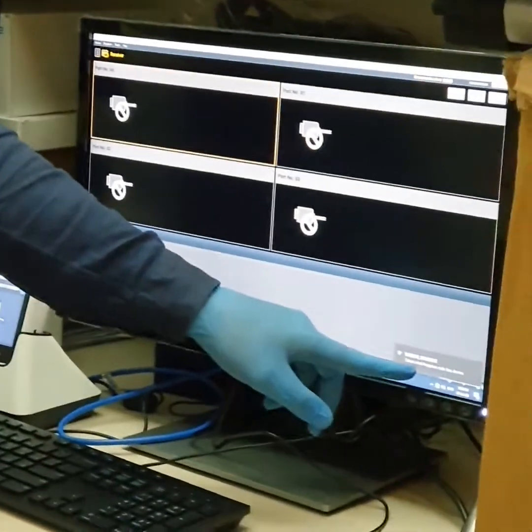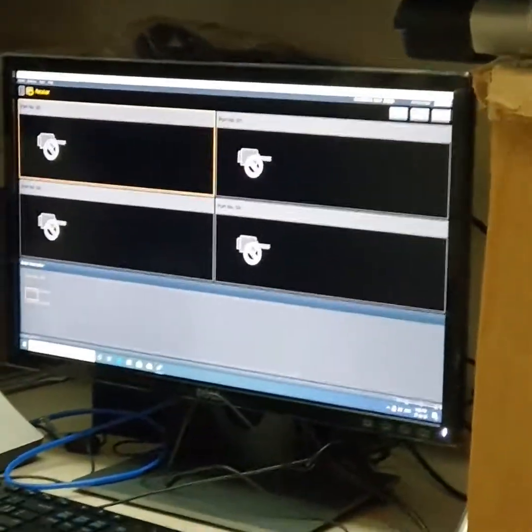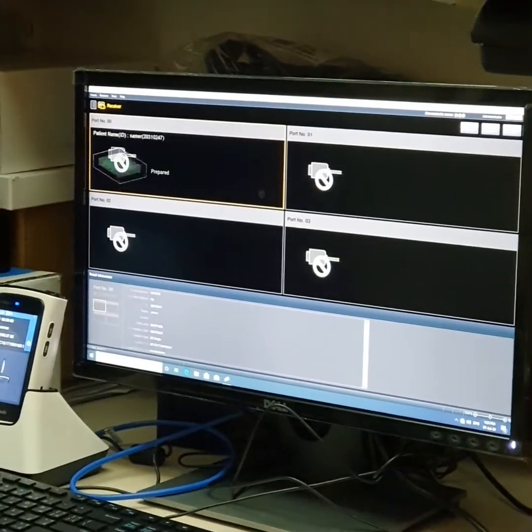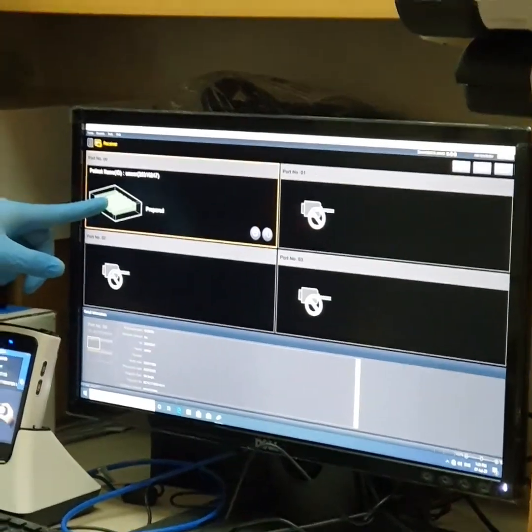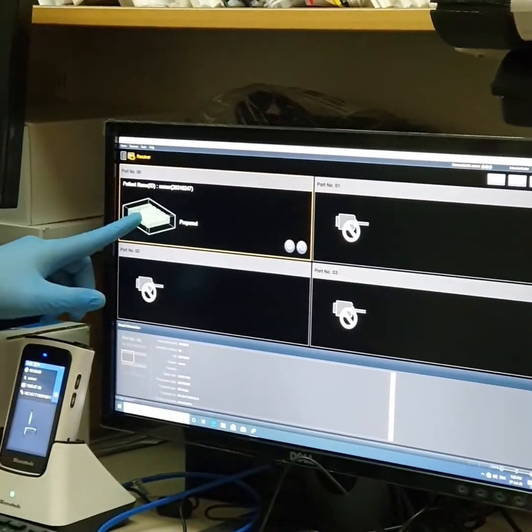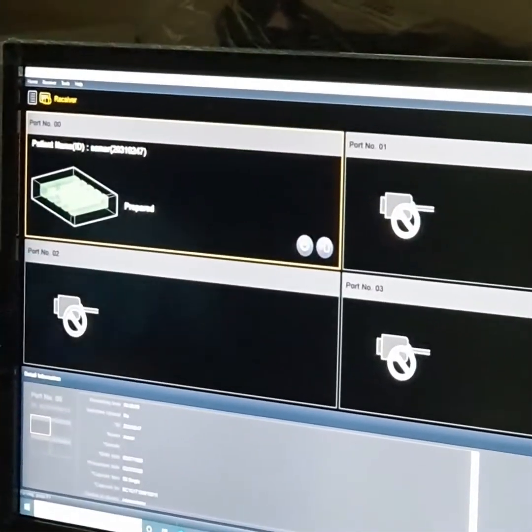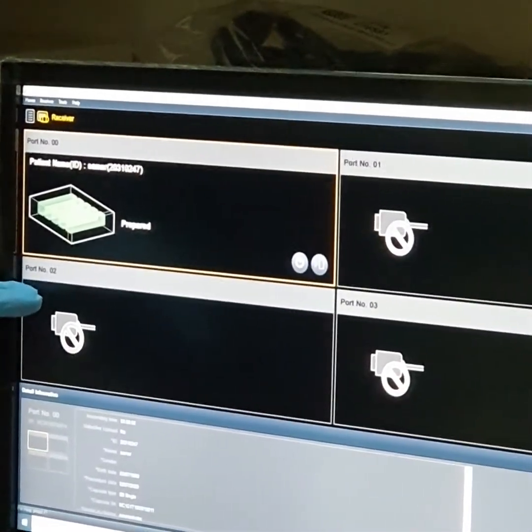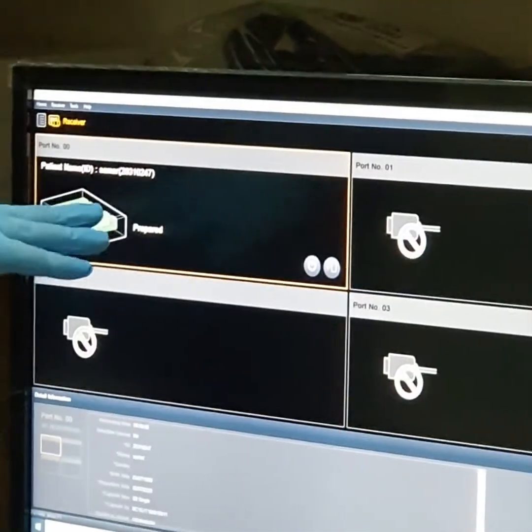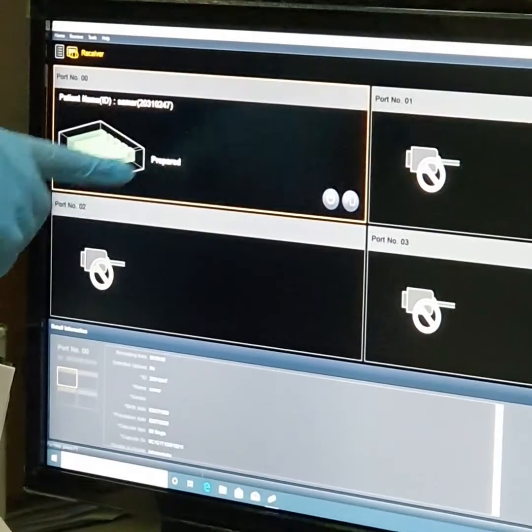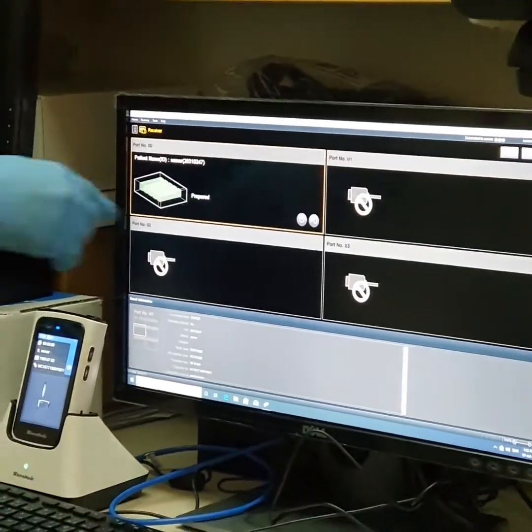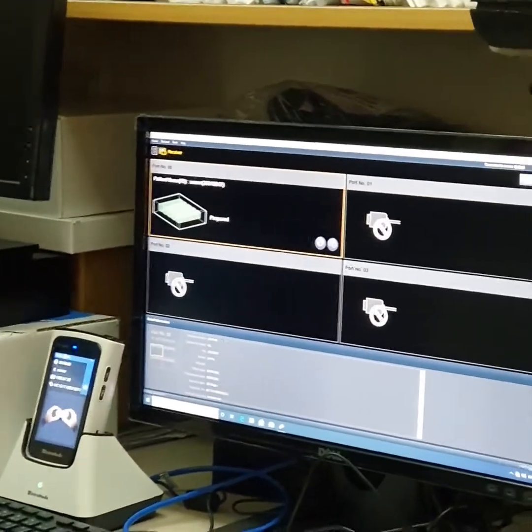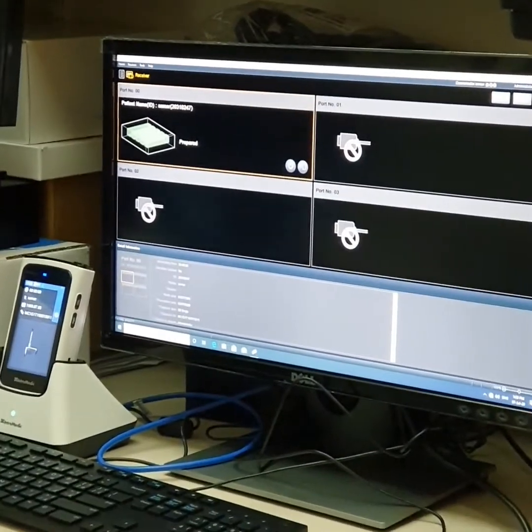The computer has recognized the receiver. The next step: the software will find which receiver should be used for the patient. What I have seen here is already prepared, because yesterday — on Thursday when we were demonstrating to the first group — we initialized the receiver.